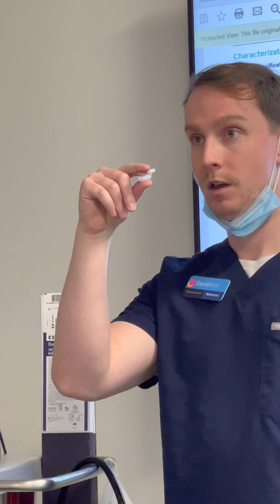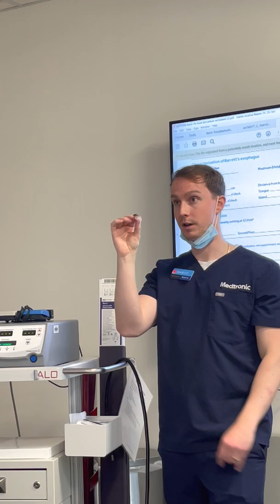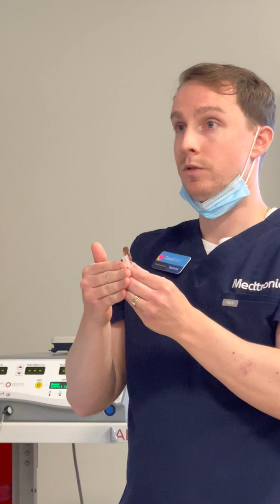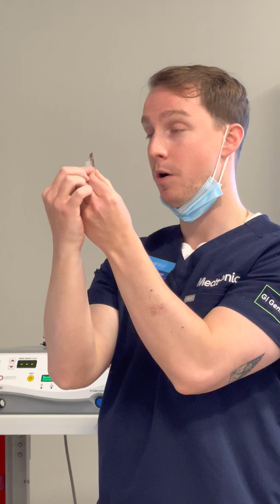What we want to do is look at the scope screen. It might be off to the side of our vision, but on the scope screen it has to look like a baseball cap. So please orient the catheter so that on the actual scope screen it looks like a baseball cap. One issue that we run into is that this rubber gasket doesn't slide all the way onto the scope, so in the vision of the scope screen you can see part of this rubber part. We want to make sure that it's flush, that this part is flush to the end of the scope.